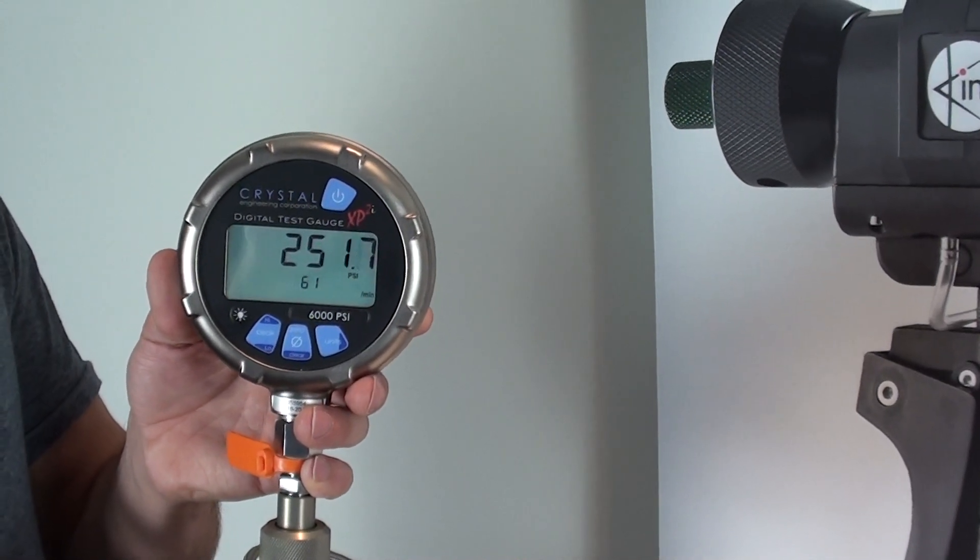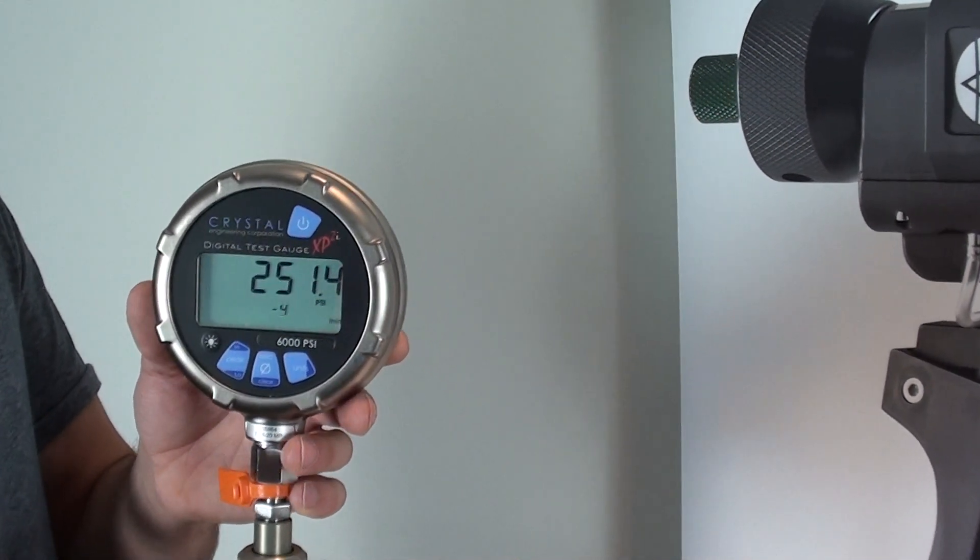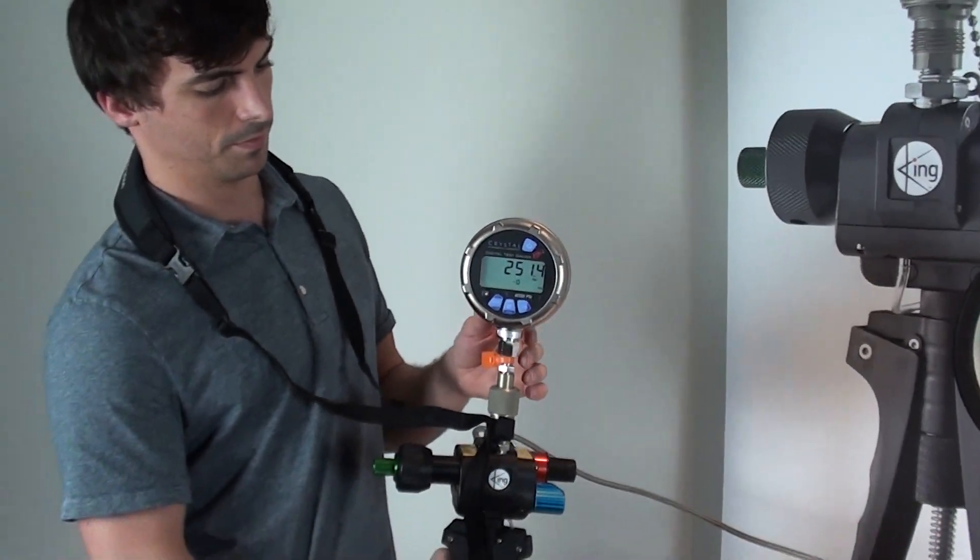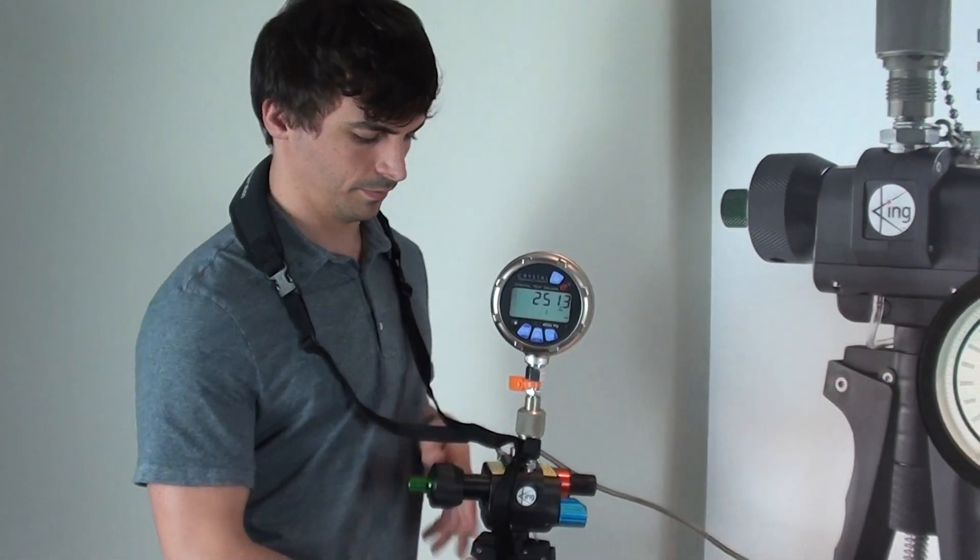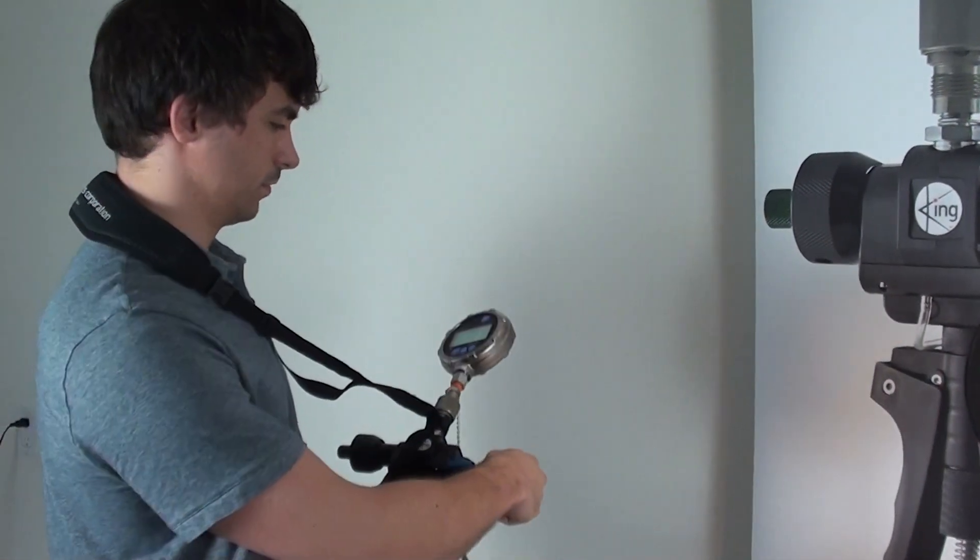So as you can see, pretty easy to get up to 2500 PSI. But to calibrate our gauge at a higher pressure, we're going to need to switch to hydraulic mode. So what we're going to do first of all, we're going to vent the pump.